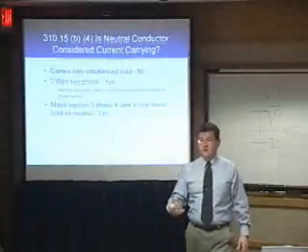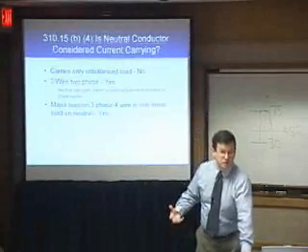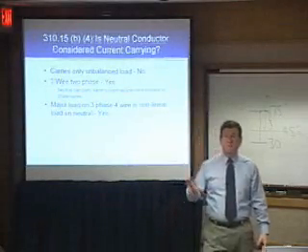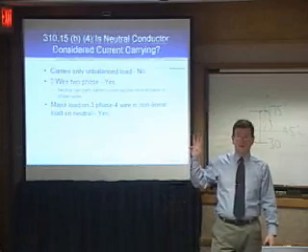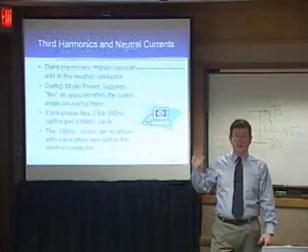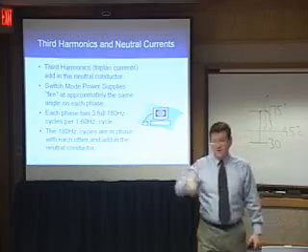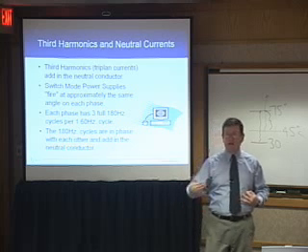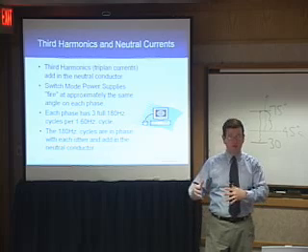A nonlinear load is a harmonic-producing load, and specifically the concern is third harmonics. Office equipment, computer power supplies — specifically switch-mode power supplies — produce third harmonic current, which is 180 Hz current. They also produce other harmonics: fifth harmonic, seventh harmonic, and many others.